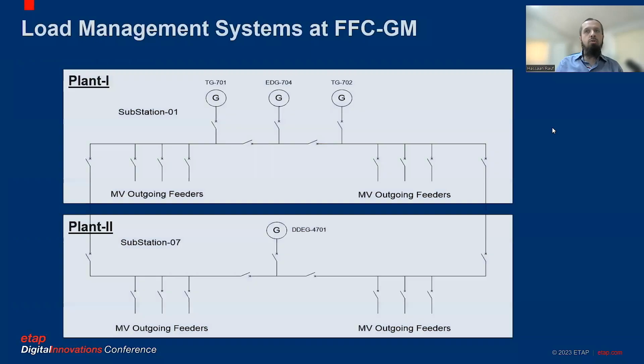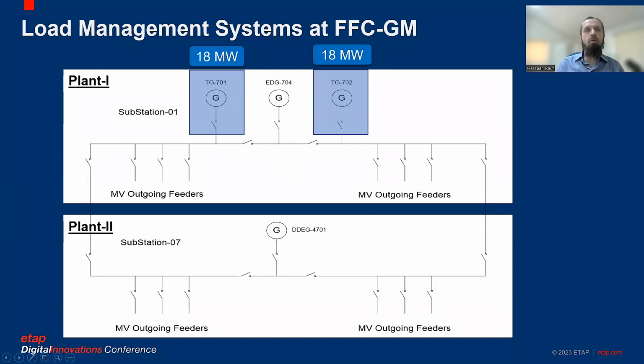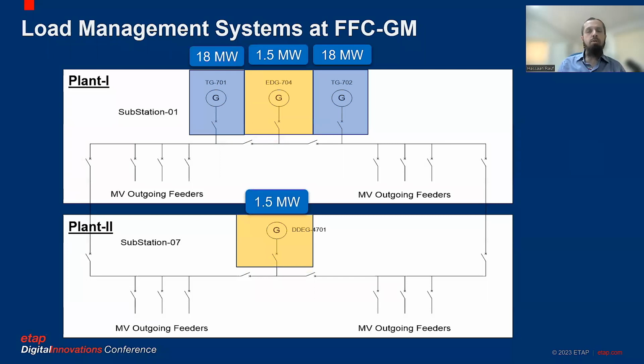So to begin with, it is imperative to have an idea of the single line diagram of the power distribution system. There are two production plants here, plant 1 and plant 2 at this site GM. This is the main substation of plant 1, which is substation 1, and another, substation 7, which is the main substation of plant 2. We have two turbo generators of 18 megawatt each, hooked up to the system at substation 1 and synchronized through the bus couplers, which remain in closed position. And then we have two emergency generators, each hooked up to its respective substation, one for plant 1 and one for plant 2.